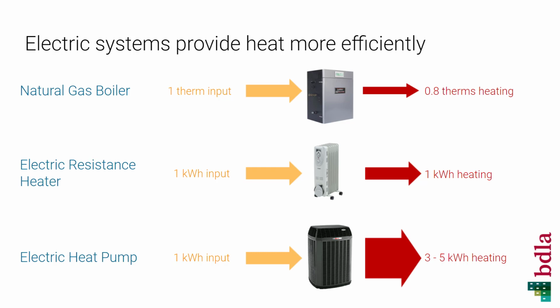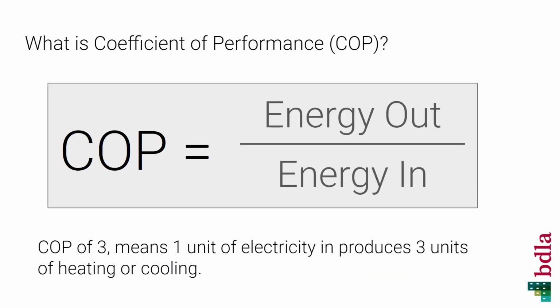And how does that actually happen? A heat pump just moves heat from one place to another instead of generating heat itself. It uses the refrigeration cycle to pull heat from outdoors and inject it into the building, which is why the efficiency can be better than 100%. For heat pumps, we don't usually refer to it as 300 to 500% efficient. We usually talk about it in terms of coefficient of performance, or COP. The COP is just the energy out divided by the energy in. So in our previous example, an efficiency of 300% would be a COP of 3, which means 1 unit of electricity is able to produce 3 units of heat.